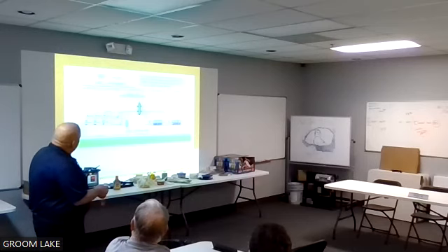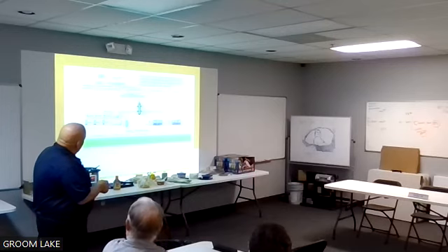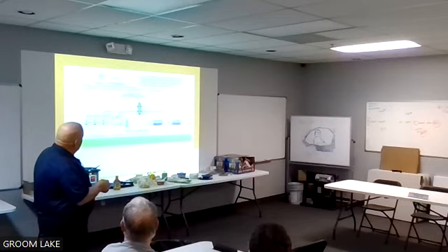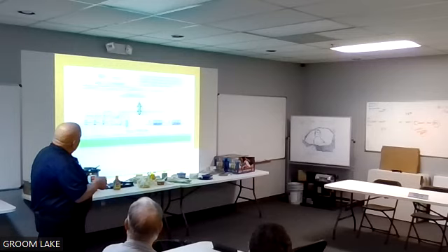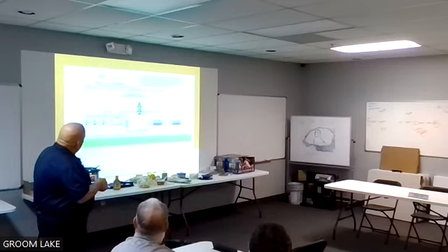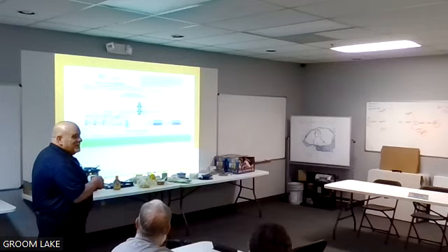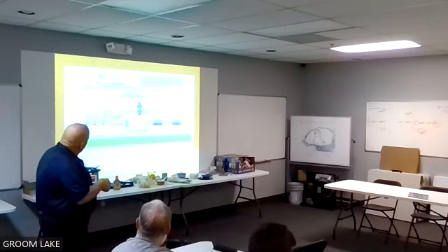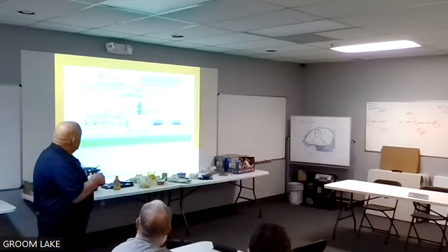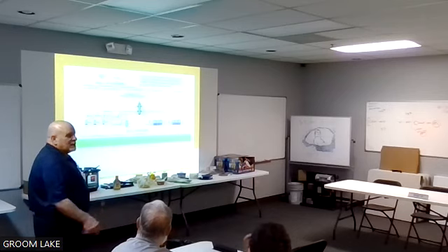So what the decoupler allows me to do is the water flows across these directly. Just treat it like a piece of pipe. Flow here and here is equal to flow this way and this way. But if this is flowing 50 GPM and this is flowing 100, this will bypass: this will take the 50 here, this will bring 100 in here, 50 up through here, and I'll still put out 100 here. It's additive. Do you follow what I'm saying? If I only have 50 over here, I come in here with 100, 50 goes this way, 50 goes that way, 50 comes back in here, I still got 100 going here. I can run two different flow rates without distracting from the other side.